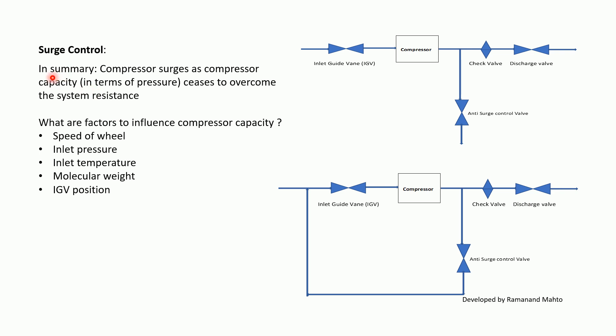As understood in the previous lecture, a compressor surges because its capacity is not enough to overcome the system resistance. The factors that influence compressor capacity are: the speed of the wheel or impeller, inlet pressure, inlet temperature, molecular weight, and inlet guide vane (IGV) position.